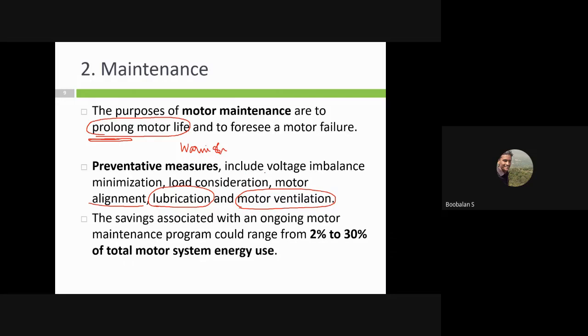One more thing is voltage imbalance, which we'll discuss later. We have R phase, Y phase, B phase. If it's a 3-phase 440 voltage motor, looking at all three phases, phase to neutral should be around 230 voltage, and line to line, R to Y, should be around 430.